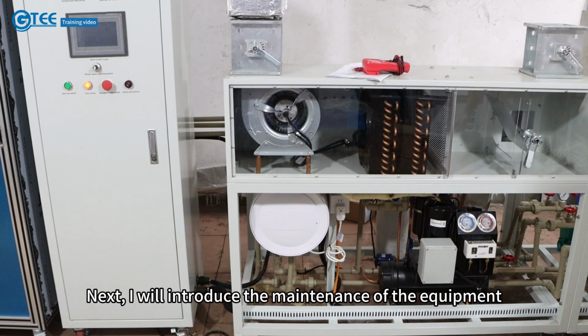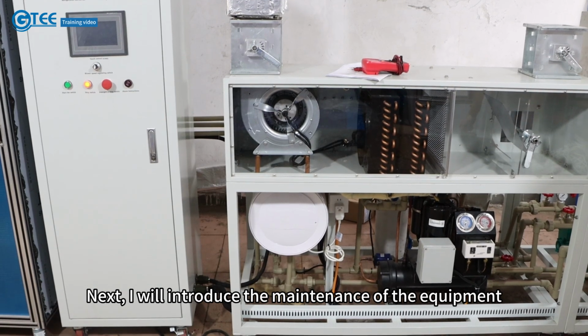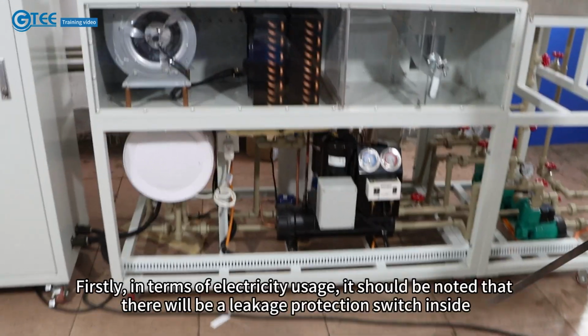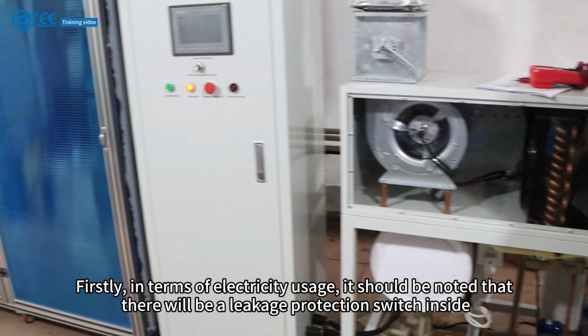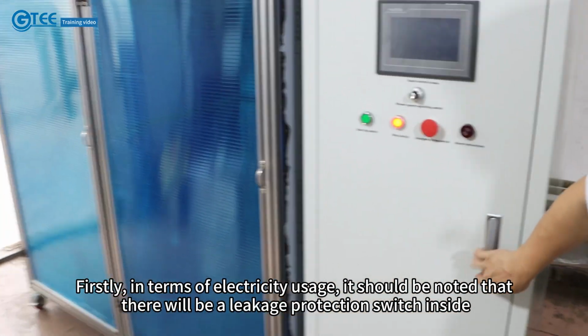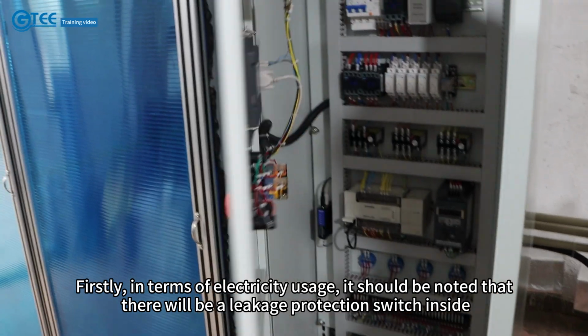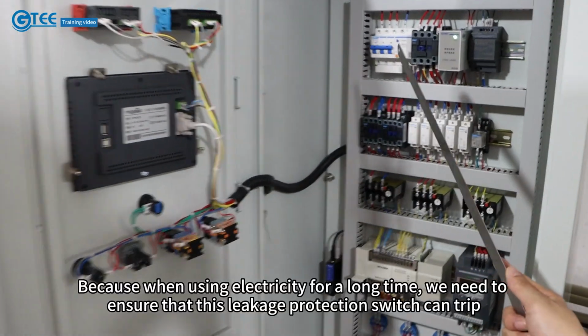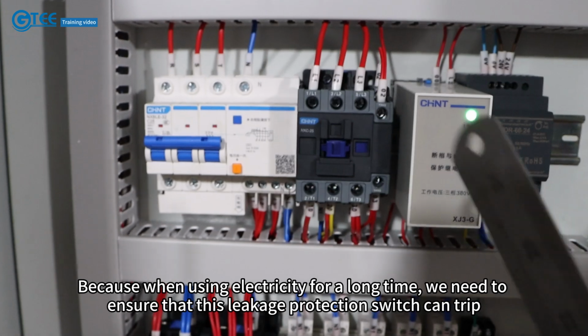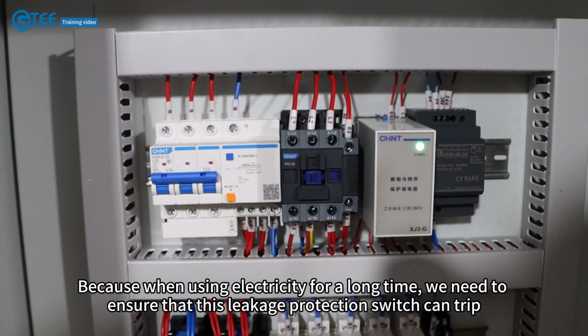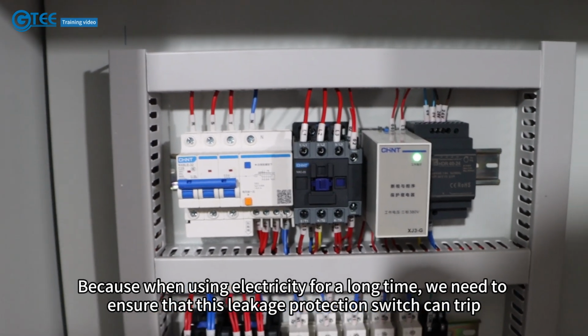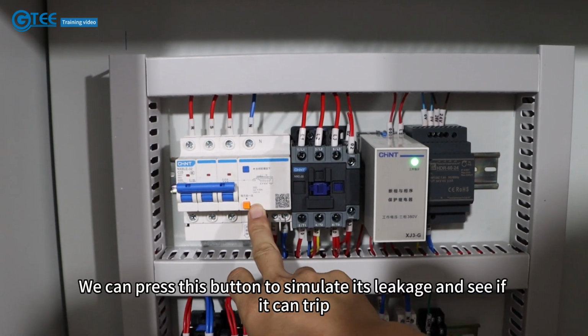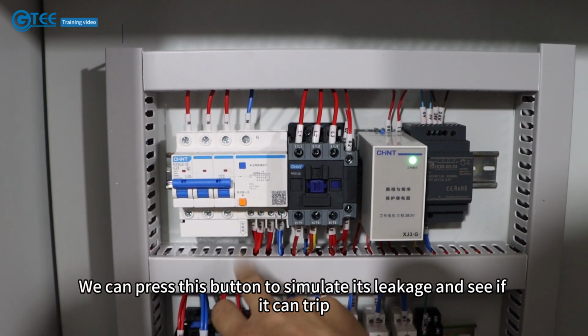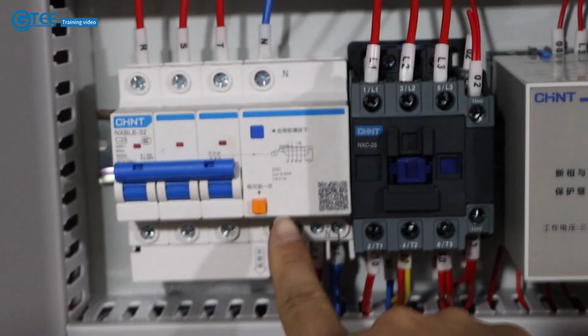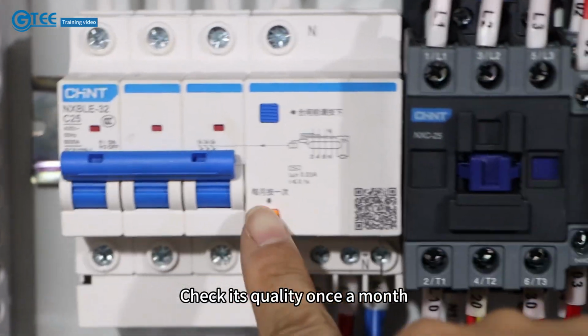Chapter 4. Equipment maintenance. Next, I will introduce the maintenance of the equipment. Firstly, in terms of electricity usage, it should be noted that there is a leakage protection switch inside. Because when using electricity for a long time, we need to ensure that this leakage protection switch can trip. We can press this button to simulate its leakage and see if it can trip. Check it once a month.